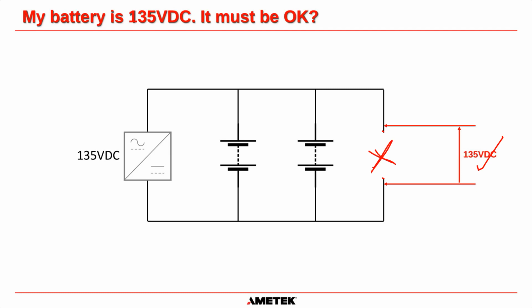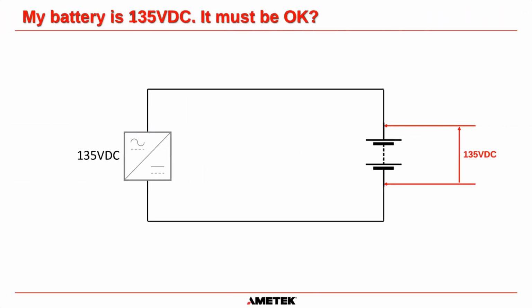So how on earth are you going to figure out the state of charge of the battery? If you remove the battery, you still get 135 volts. That voltage is the voltage of the charger. That's all it is. It has nothing to do with the state of charge of the battery whatsoever. So if we didn't have 3 batteries in parallel, we just had 1 battery, we would measure 135 volts DC. If there was an internal problem, or if you remove that battery completely, 135 volts DC. If there was an open circuit cell in that battery, you would still measure 135 volts DC. The voltage of the battery does not tell you anything about the state of charge of that battery. Biggest maintenance mistake.